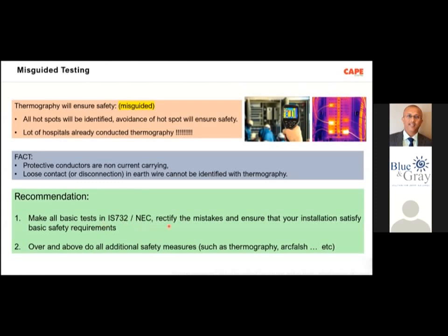Basically, the recommendation is you must do the testing as per IS 732 and the National Electrical Code as the first safety measure. The first electrical safety measure is to ensure that your installation conforms to these two standards. Over and above, you can do additional safety measures such as thermography and arc flash as extras. But I will put it one more way: if you don't do the basic tests, and do only thermography and arc flash, and expect electrical safety in your building, you are actually fooled. You cannot achieve safety. You must have conformation to IS 732 and NEC.